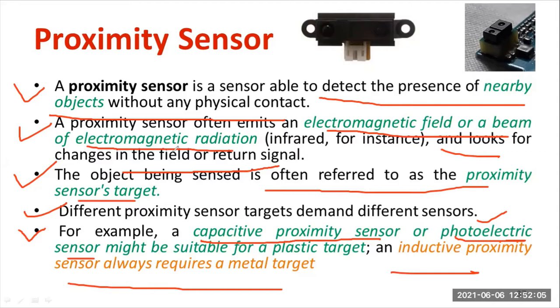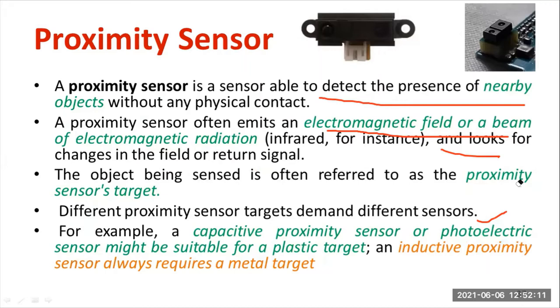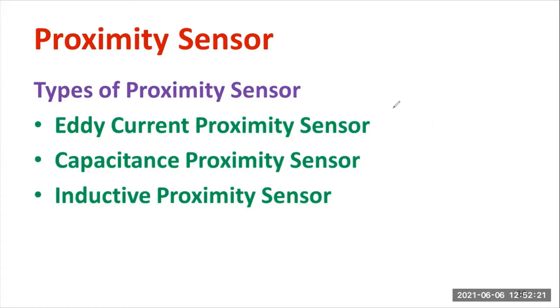A proximity sensor is a device used for measuring the presence of a nearby object. You can classify proximity sensors into three types: eddy current type, capacitive type, and inductive type. Eddy current and inductive type proximity sensors are similar and are used for detecting the presence of metal bodies, whereas capacitive type proximity sensors are majorly used for non-metal objects such as rubber and plastic.